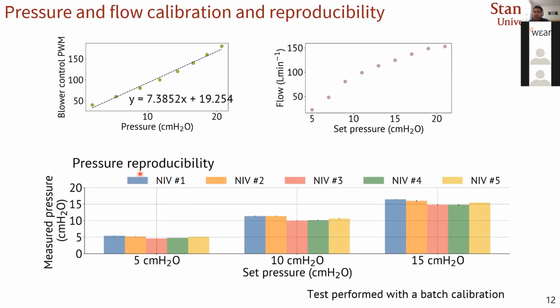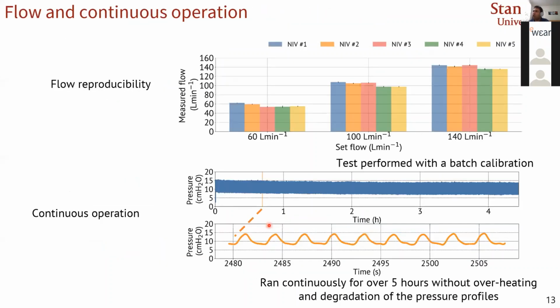And as I mentioned, we made 5 devices, and we had to check the reproducibility. And we did a batch calibration, so it's not device-to-device calibration. For one batch, we just use this calibration curve. And what we saw is we can actually get a good amount of reproducibility even from device to device. Same goes for flow. We can do 60 liters per minute, 100 liters per minute, and 140. And also we tested the unit for 5 hours. So here I'm showing its running time is 5 hours. We can even go higher.